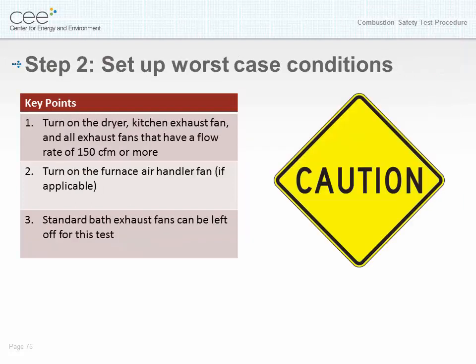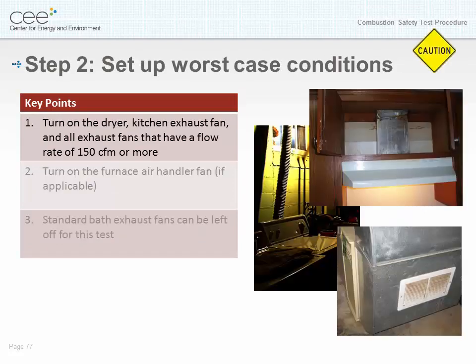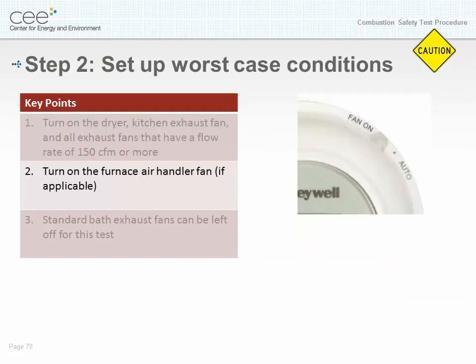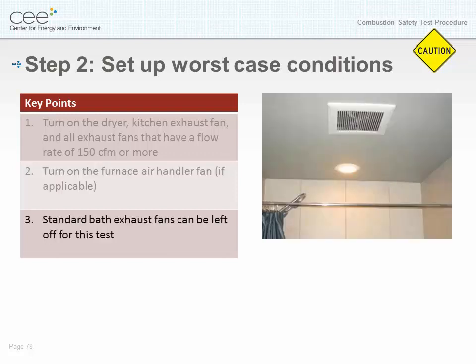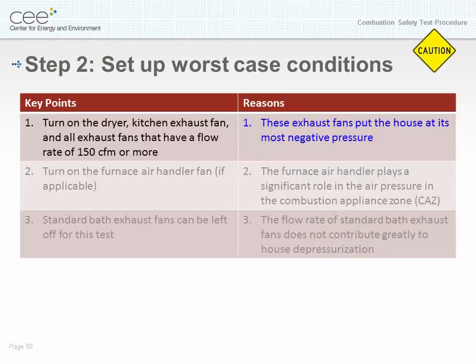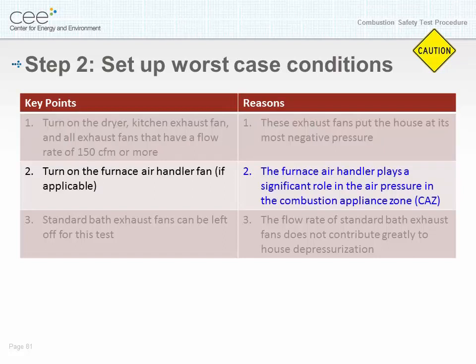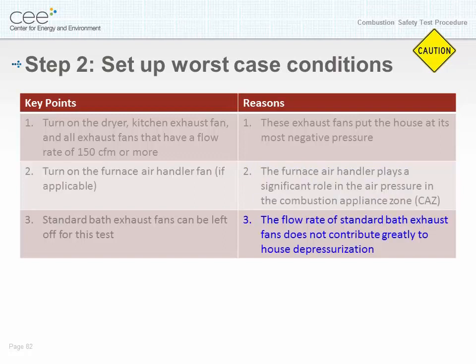Step two: set up worst case conditions. Key points: number one, turn on the dryer, kitchen exhaust fan, and all exhaust fans that have a flow rate of 150 CFM or more; number two, turn on the furnace air handler; number three, standard bath exhaust fans can be left off for this test. The exhaust fans put the house at its most negative pressure. The furnace air handler plays a significant role in the air pressure in the combustion appliance zone. The flow rate of standard bath exhaust fans does not contribute greatly to house depressurization.